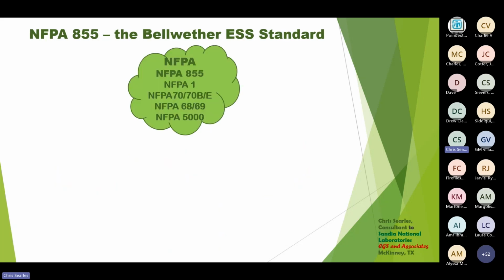Let's dive a little deeper. So we have NFPA 855 as the bellwether, but remember I said there were reference standards within the codes, and even within the standards we have references to other standards. In the NFPA case, we have the fire code. We also have the National Electric Code, and two subsets of that: the maintenance code, and worker protection and safety code 70E, which deals with arc flash and PPE and things of that nature.